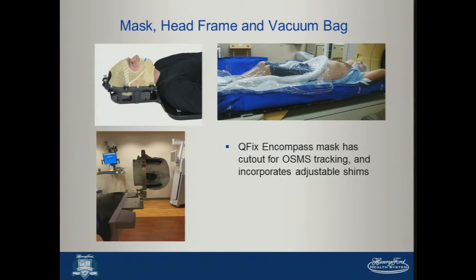In terms of immobilization devices, thermoplastic mask is used for the bulk of cranial cases. What you see here is a mask with a face cutout to accommodate the optical surface monitoring system for cranial treatments. The optical surface monitoring system is looking at the exposed part of the patient's face and using the cheekbones, etc., to monitor motion in 6D. I'll have another slide on that shortly. There is the head frame, which we'll use for certain functional treatments. And for SBRT treatments, we're using the blue bag with or without that plastic wrap to suppress or reduce the breathing motion somewhat.